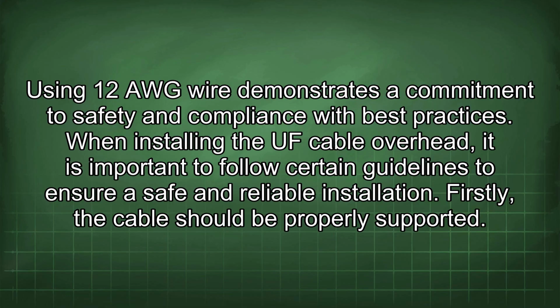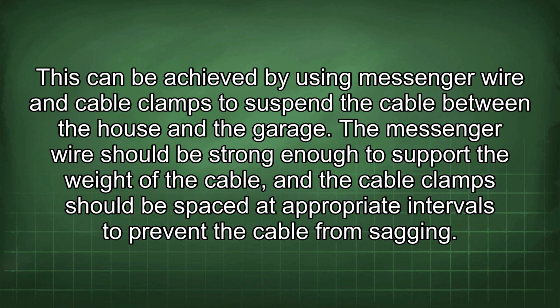When installing the UF cable overhead, it is important to follow certain guidelines to ensure safe and reliable installation. Firstly, the cable should be properly supported. This can be achieved by using messenger wire and cable clamps to suspend the cable between the house and the garage. The messenger wire should be strong enough to support the weight of the cable, and the cable clamps should be spaced at appropriate intervals to prevent the cable from sagging.